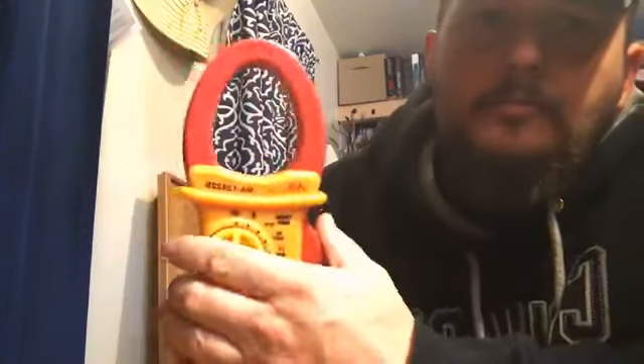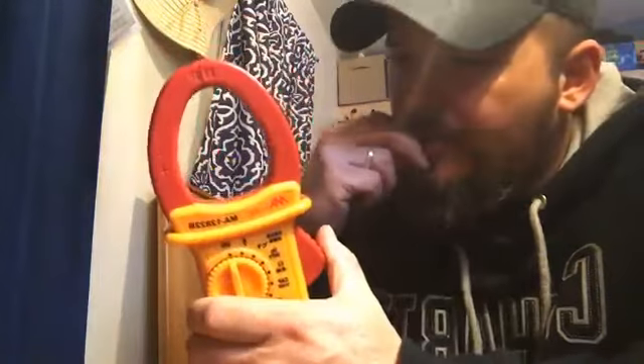And that's amperage, using the clamp. Anytime something is drawing electrical power, it's drawing amperage. The more it's drawing, the higher the amperage draw, and there's an expected amperage draw with certain components. If I'm looking at a bake element on an oven, I'm typically looking for somewhere between 12 and 15 amps. That's another way we check.